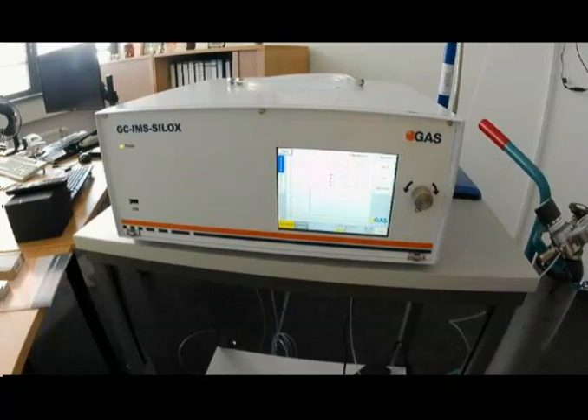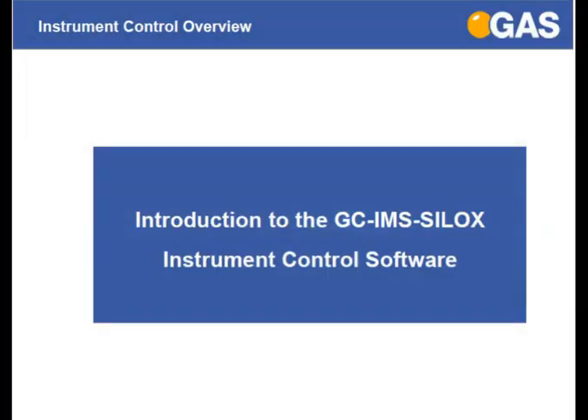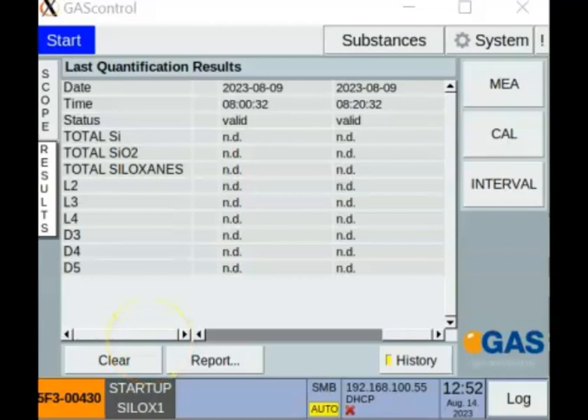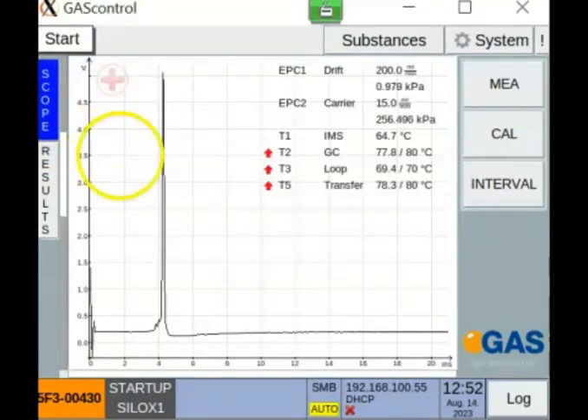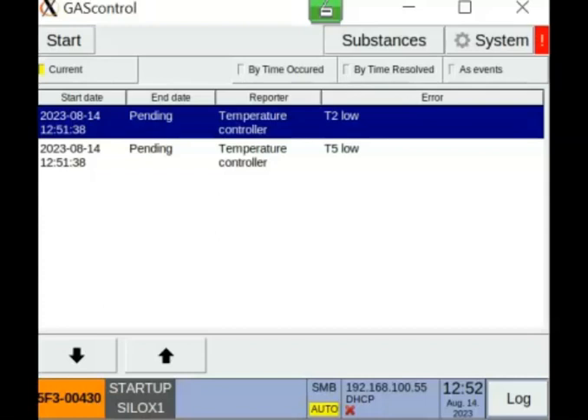For instrument control purpose, it's also possible to use the USB port as an input as well as an output port. We can upload new firmware, we can upload a measurement tag list, or we can export the result report or the measurement files. This is the screen after booting. We can switch from the results view to the scope view, and we see that the temperatures are still raising, and this is causing the blinking here, the error message. The error message will disappear as soon as the temperatures are reached.